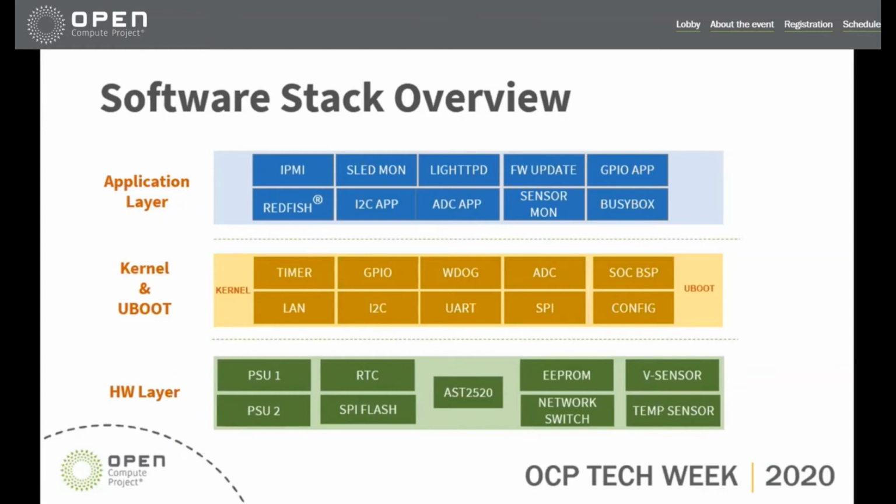Next is the Redfish layer, which provides the RESTful interface. In this design, various sensor and SLED information is gathered by the IPMI layer. Then this information is also consumed by the Redfish layer for monitoring purposes using the REST interface. The control actions generated by the Redfish interface are serviced by the IPMI layer.